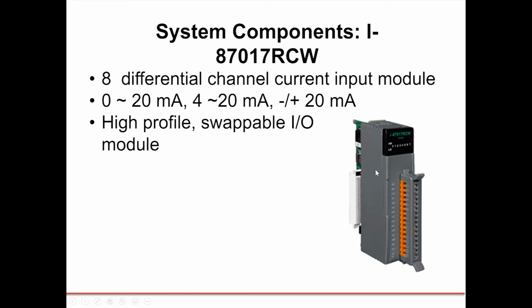The other slot I/O module that we talked about was the I87017 RCW. It's an 8-channel current input module specifically designed to measure current only. It has 8 differential channels, and thanks to its built-in resistor, you can measure the current directly. It's also suitable for harsh environments since it has 4 kilovolt ESD protection and plus/minus 200 volt DC common voltage as current input protection. It also features 3000 volt DC intermodule isolation together with open wire detection for 4 to 20 milliamp input.